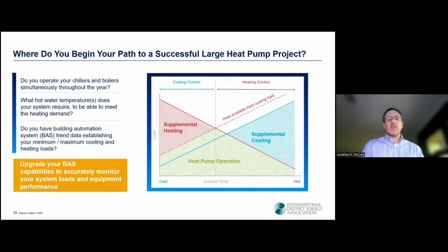So there's a base load of cooling in the winter and a base load of heating during the summer. If you do have that situation in your system, you're very likely a great candidate for a large heat pump. So the next thing I would ask is, what temperature does your system require on the hot water side? Really what we're trying to answer here is, is your system able to operate with the temperatures that are currently available with today's heat pump technology?